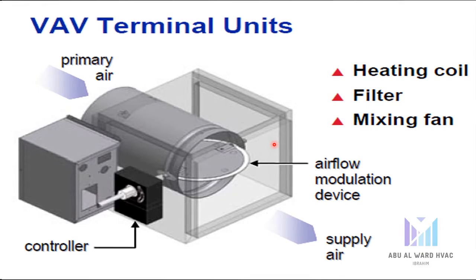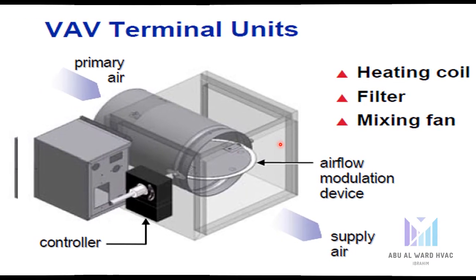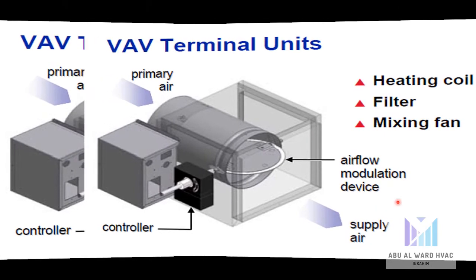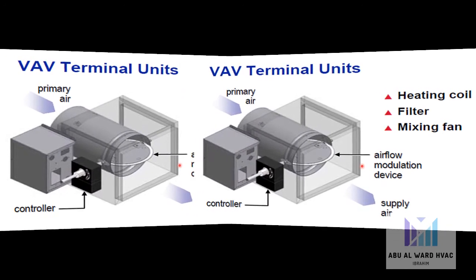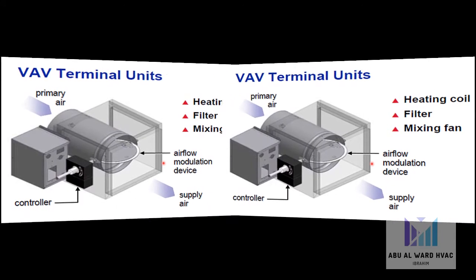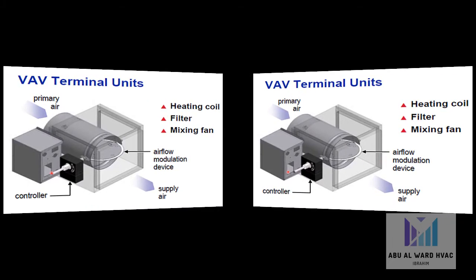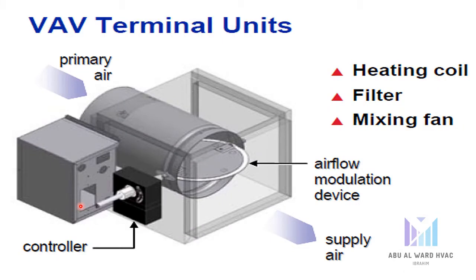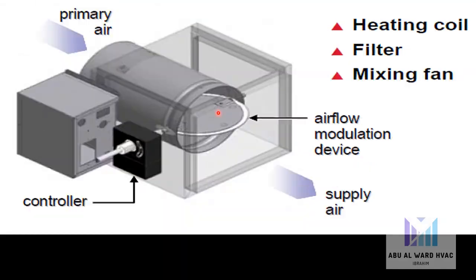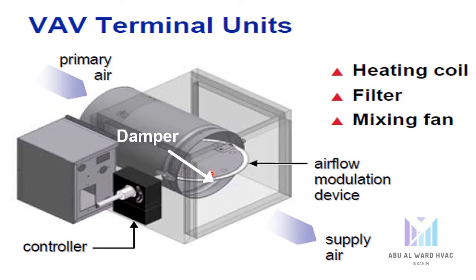A VAV terminal unit is a sheet metal assembly installed upstream of its respective space diffuser. The unit consists of an air modulating device, control hardware, and depending on the system application, possibly a heating coil, a filter, and a small terminal mixing fan. Modulating the airflow to each individual space is accomplished using a temperature-controlled mechanical device that varies the airflow resistance in the supply duct. The rotating blade damper changes airflow resistance by rotating the damper into the air stream, restricting the size of the air passage to that space.